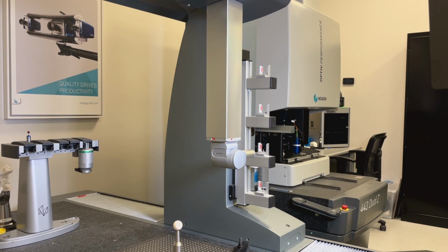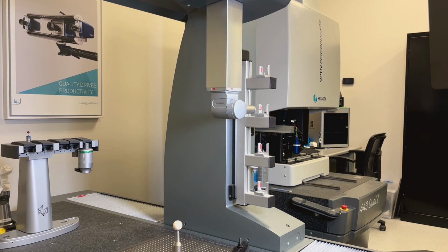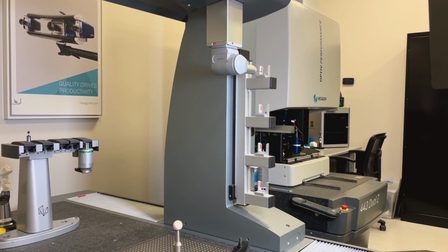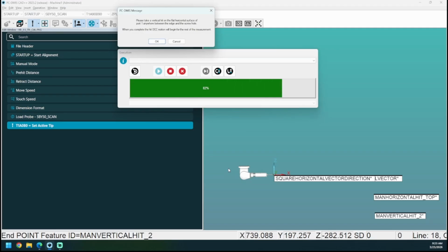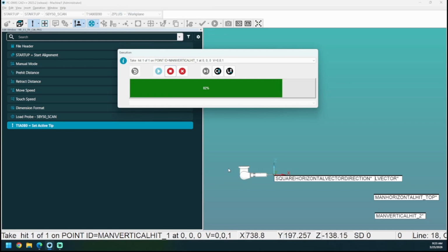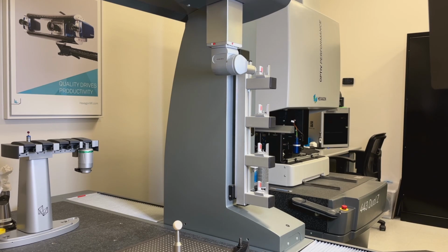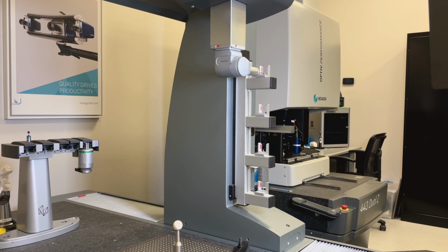And then once I take my last hit on port 1, PC-DMIS will tell me to please take a vertical hit on the flat horizontal surface of port 1 anywhere between the edge and the screw hole. When you complete the hit, DCC motion will begin for the rest of the measurement. So once I hit OK after taking this last vertical hit, PC-DMIS will go through and measure the rest of the ports for a full calibration.